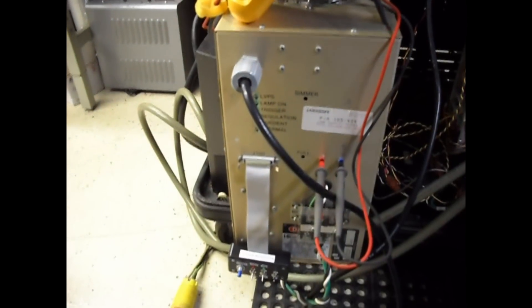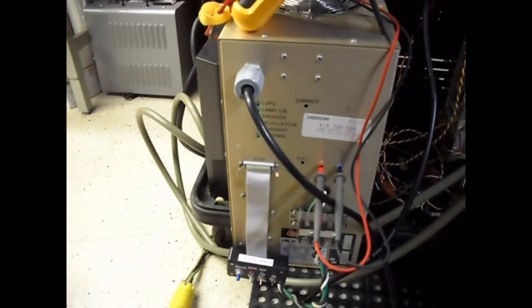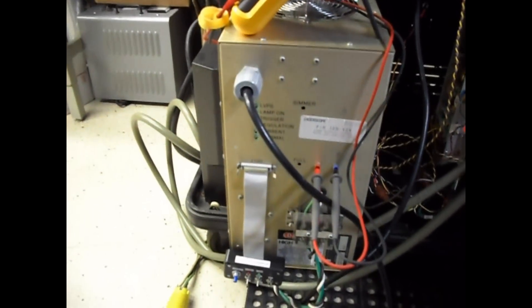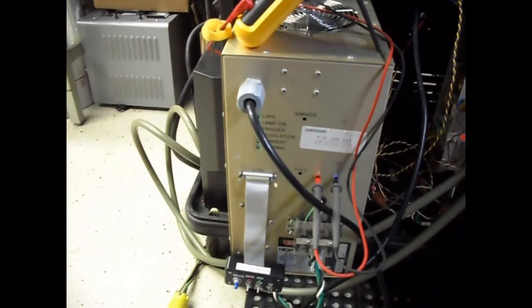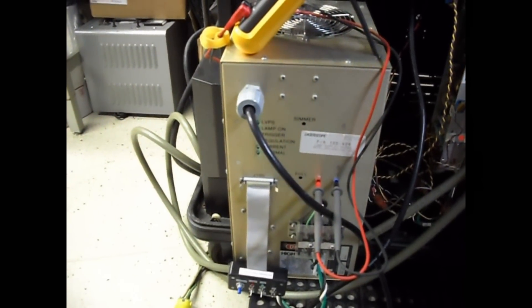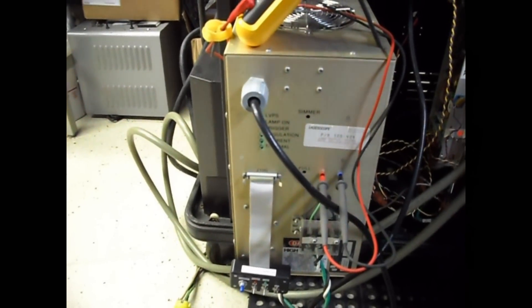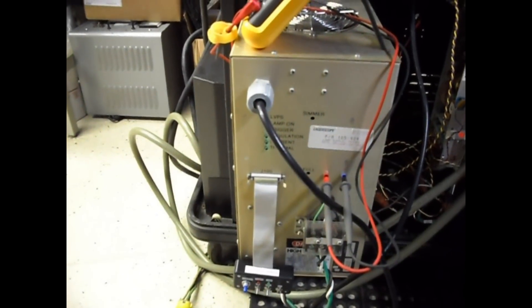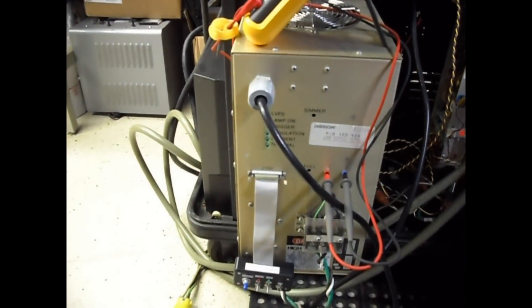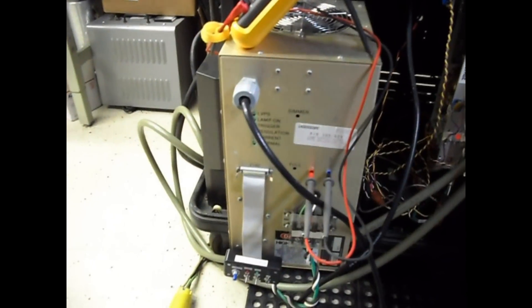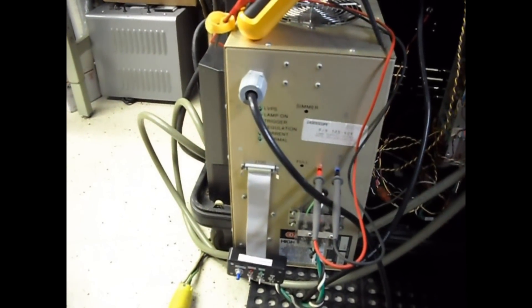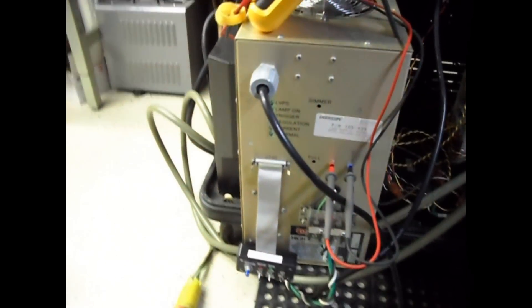That's just a low frequency power supply, 5 volts, 24 volts, just like you'd find in a computer power supply. Over here, this big gold box right here, this is basically the lamp supply for the YAG rod. This is what powers the lamp that's in the head, and it makes quite a bit of current. The idea is that it runs the lamp at a nice stable current so it doesn't overheat and explode.